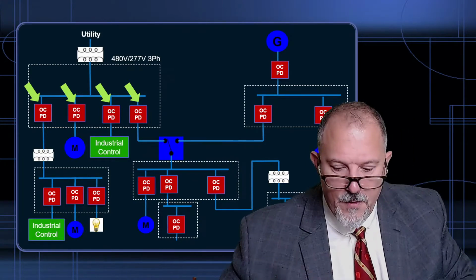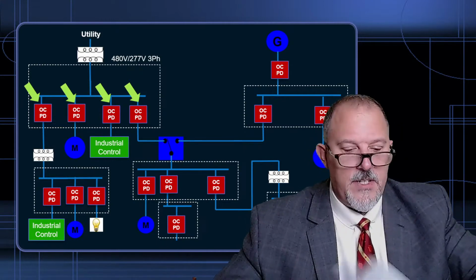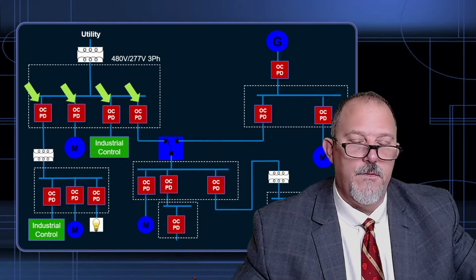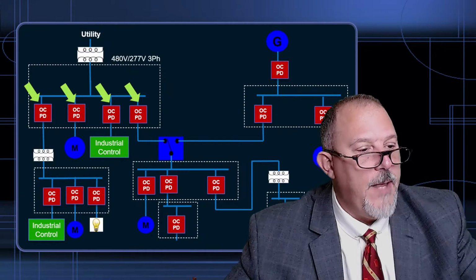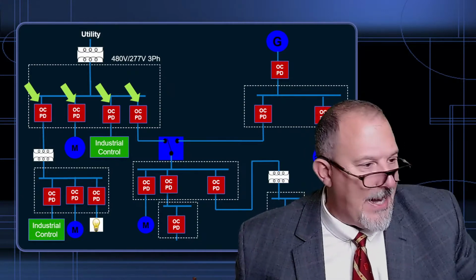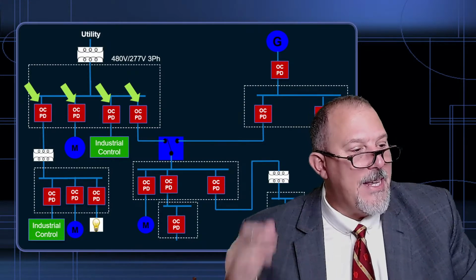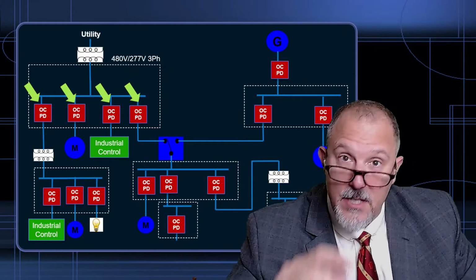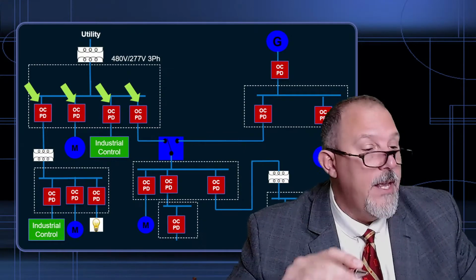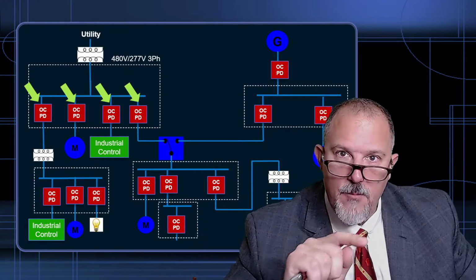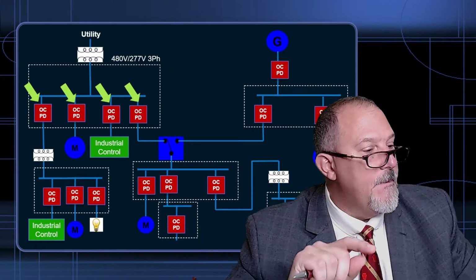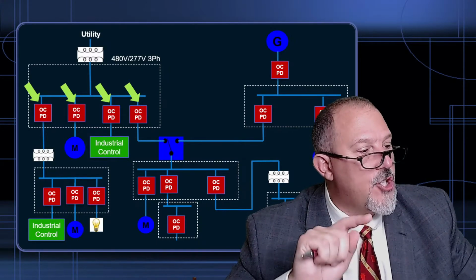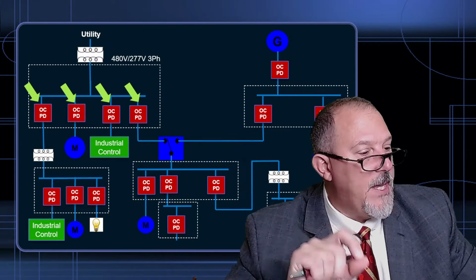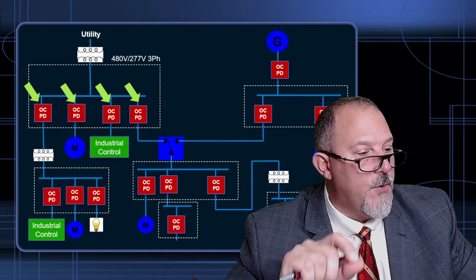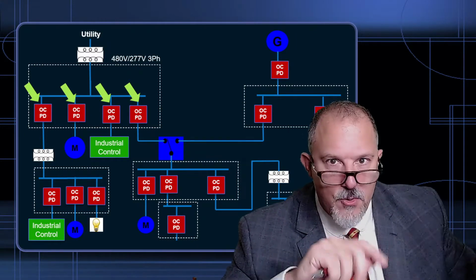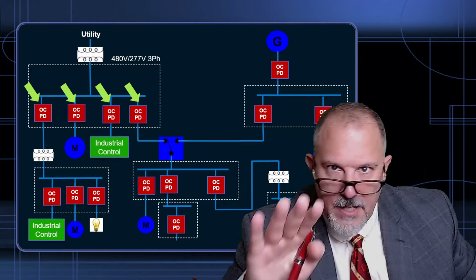And remember, that information that happened in the 2017 code is very relative to Table 130.7(C)(15)(A), the arc flash PPE category for alternating current systems. This is the table method. And if you're familiar with 70E and you go to Table 130.7(C)(15)(A), it says panelboards or other equipment rated greater than 240 volts and up to 600 volts. It's a table, so it's all different types of equipment.